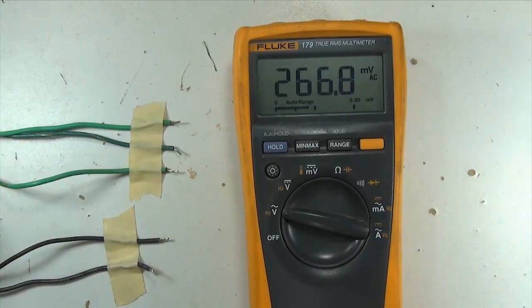Now if you ever think of working a transformer without a fuse and you happen to short the secondary, you're going to cause some problems. The wires or the transformer will get very hot, possibly melting the protective coating on the wires causing a short. Now you'll notice that the resistance measurements were very low on the secondary winding. Don't be fooled by that low resistance. If the winding was short, we would measure 0 ohms. So you would have then a bad transformer. So make sure you calibrate your digital multimeter before making a resistance measurement, and using the best possible range for making that measurement.